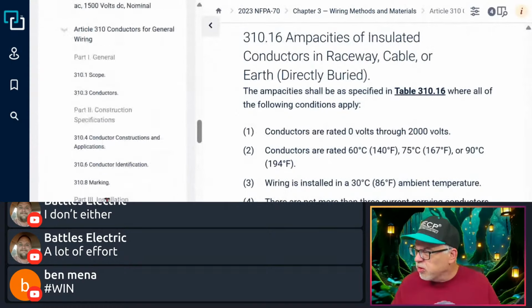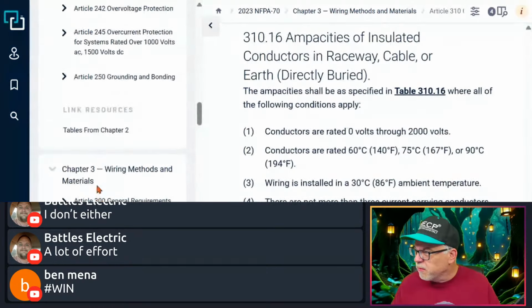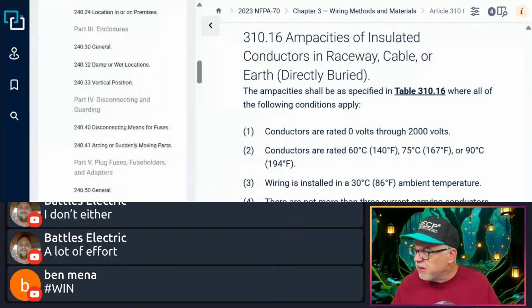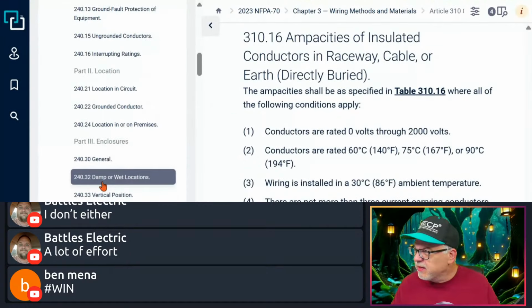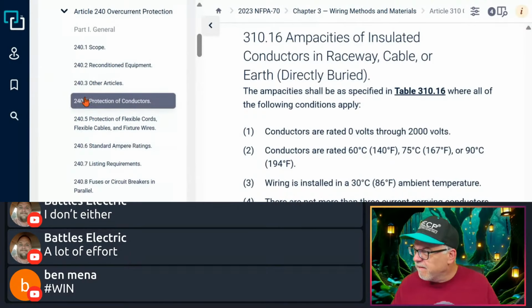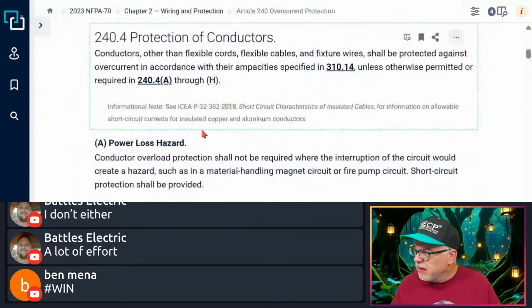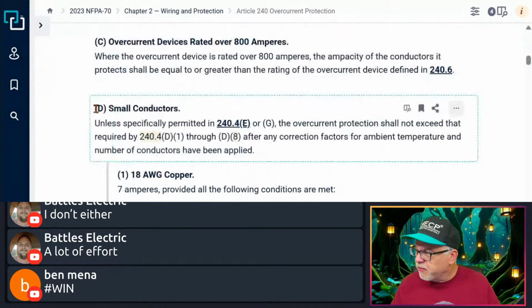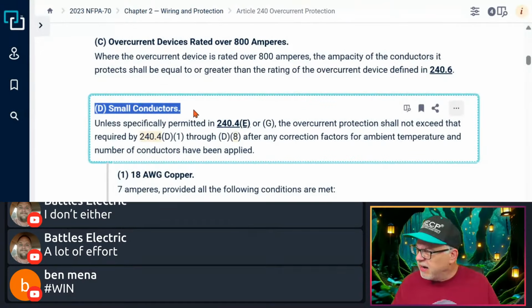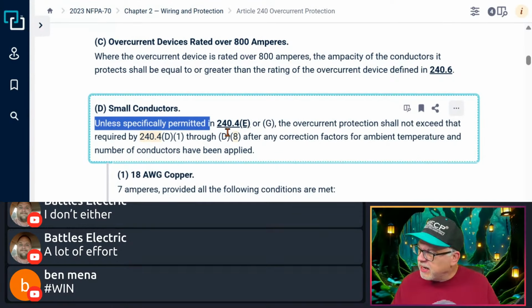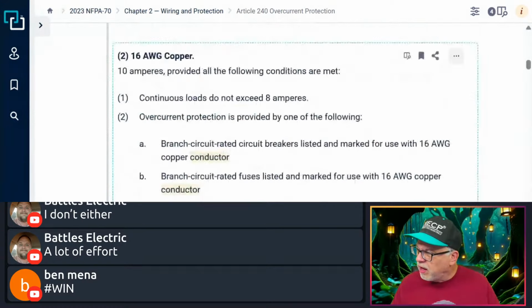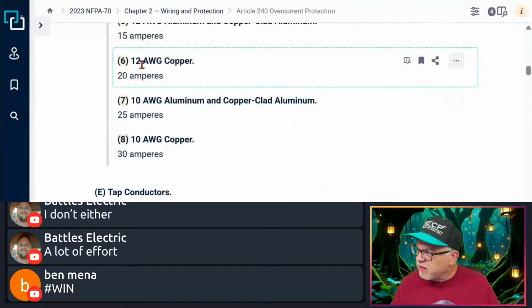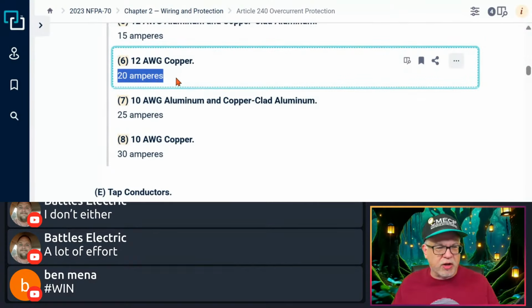So then we're going to go over to look at the small conductor rules, all right? And this is, by the way, going to segue to your answer, Brandon. So I know I'm keeping you here. So we go over here to the small conductor rule. Here's what it referenced, 240.4(D), right? Now it says, unless specifically permitted in 240.4(E) or (G), the overcurrent protection shall not exceed that required in 240.4(D)(1) through (D)(8). And we said 12, so it seems like 12 would be limited to a 20 amp overcurrent device.